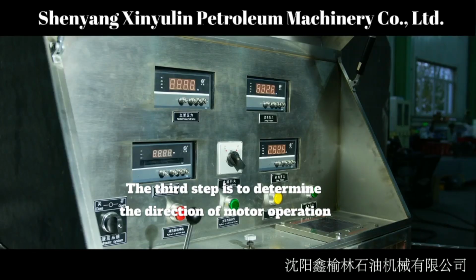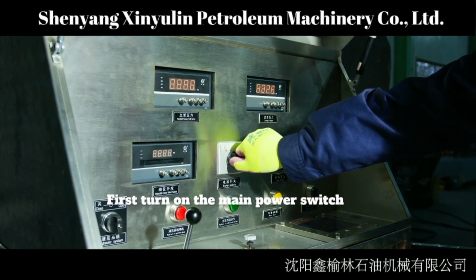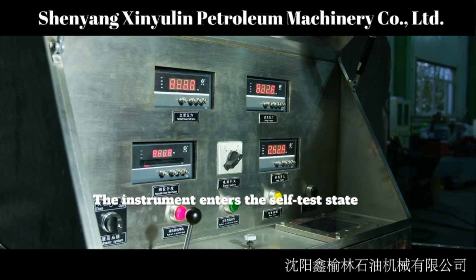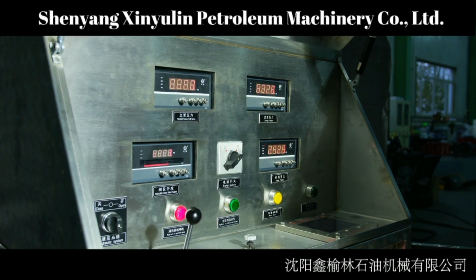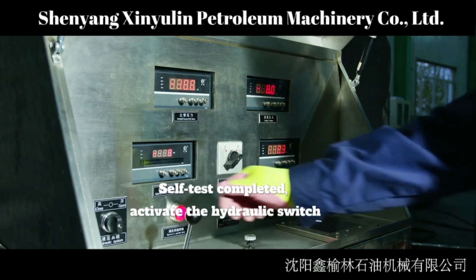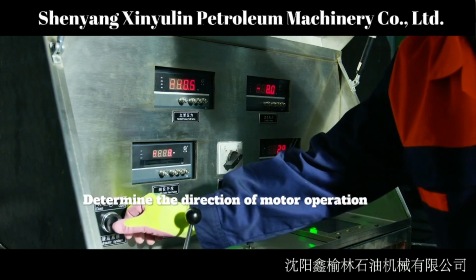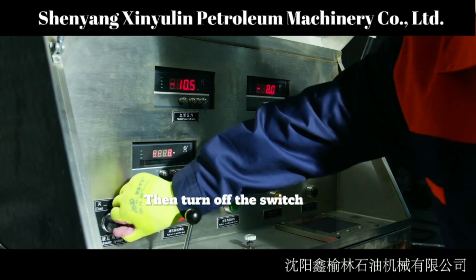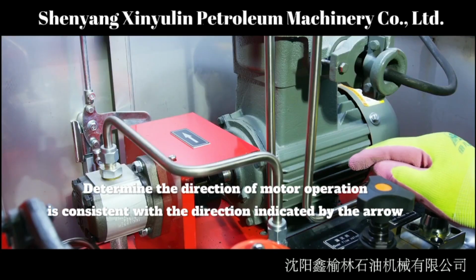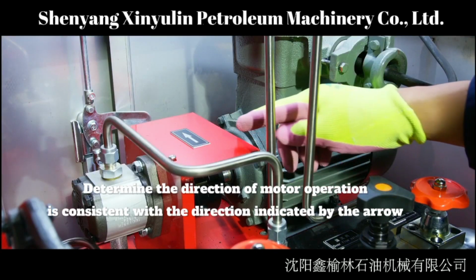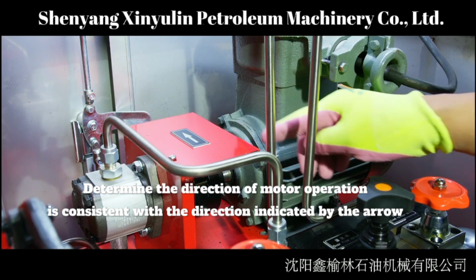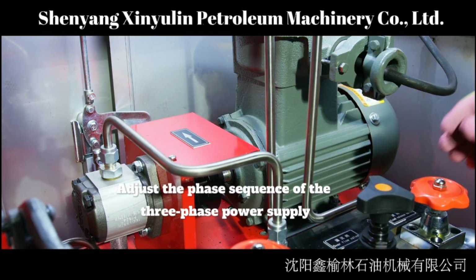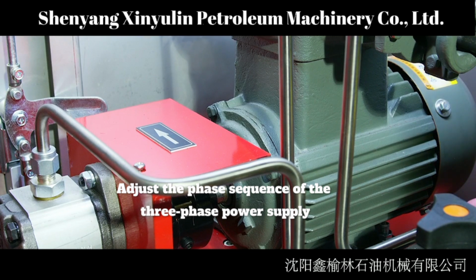The third step is to determine the direction of motor operation. First, turn on the main power switch. The instrument enters the self-test state. Self-test completed. Activate the hydraulic switch. Determine the direction of motor operation. Then turn off the switch. Determine whether the direction of motor operation is consistent with the direction indicated by the arrow. If inconsistent, adjust the phase sequence of the 3-phase power supply.